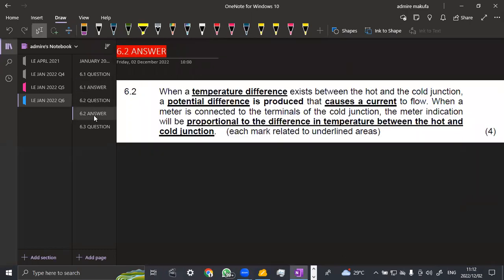When the temperature difference exists between the hot and the cold junction, a potential difference is produced. That causes a current to flow when a meter is connected to the terminals of the cold junction. The meter indication will be proportional to the difference in temperature between the hot and cold junction.